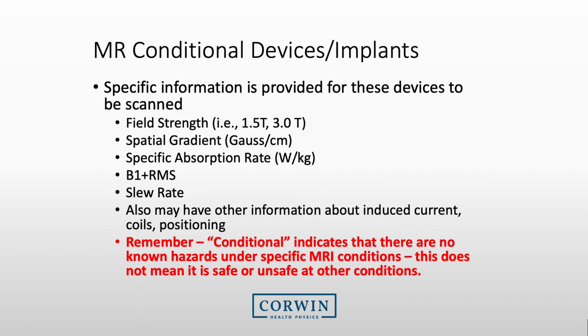Now we do our best to prevent any items from entering the MRI room that shouldn't, but many patients have implants or devices that may be present during the MRI exam. These are what we call MRI conditional devices or implants. Each device will have specific conditions in which it may be used within the MRI room during scanning. Ensure you research each specific item. A typical list of conditions is listed here. Note that conditional only indicates that the device or implant has been tested under those specific conditions and does not mean it is safe or unsafe at other conditions.